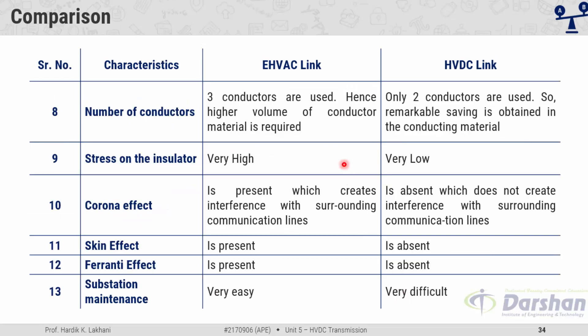In EHV AC, one circuit of a three-phase system requires three conductors, meaning a higher volume of conductor material. In bipolar HVDC, only two conductors are required, giving a remarkable saving in conducting material. Stress on insulators is very high in AC link but very low in DC. Corona effect is present in AC and creates interference with surrounding communication lines, but is absent in HVDC. Skin effect and Ferranti effect are both present in AC link but absent in DC link.